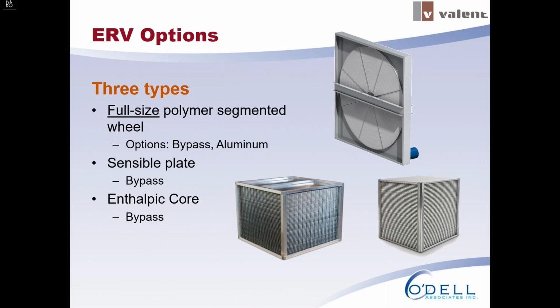And then thirdly is the enthalpic core, which is a polymer-based enthalpy core, a static core that does both sensible and latent recovery. Where we're seeing a lot of interest in that is twofold. One, obviously with COVID-19, people are concerned about any exhaust air transmission or cross-contamination from the exhaust air stream to the supply air stream. But the other area is on the maintenance side of buildings, where a facility may or may not have an on-staff facilities manager that can maintain the wheels or wants to maintain the wheels. This core is a static device, so it really reduces the requirement for maintenance.